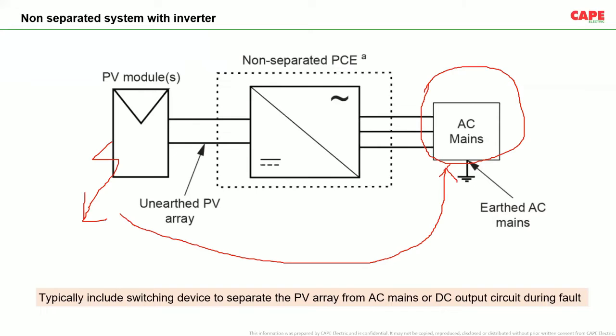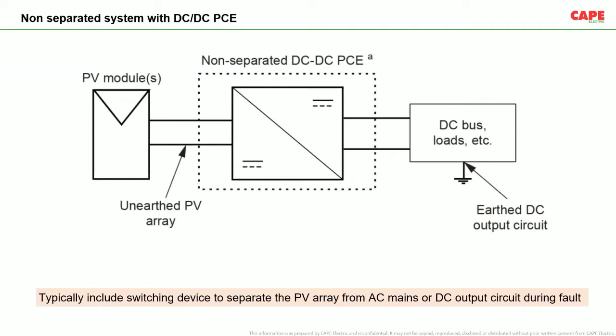The safety measure recommended is, if there is a current measurement, or if you find that, say for example, on the PV side the insulation resistance is lesser than a certain limit, you should disconnect the AC supply, in order to have safety from an earth fault or from a fault at the DC side of the PV array. We have to disconnect the AC side in this particular case, because by disconnecting the AC supply, the return path is disconnected. As a result, the chance of fire is minimized. This system also works with a DC-DC converter, with the same method. So you have a non-separated DC-DC inverter, and in case of fault, you are supposed to disconnect the incoming supply.